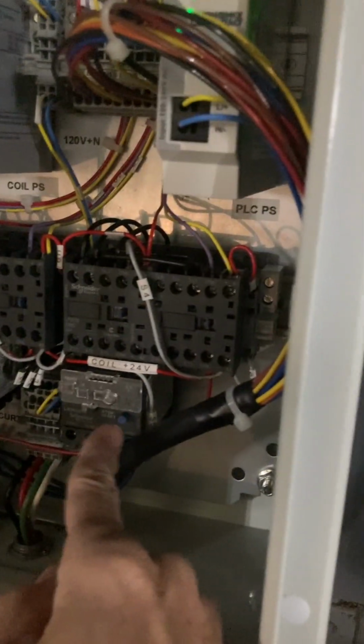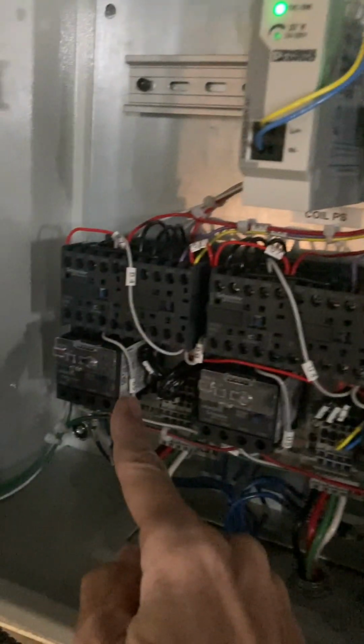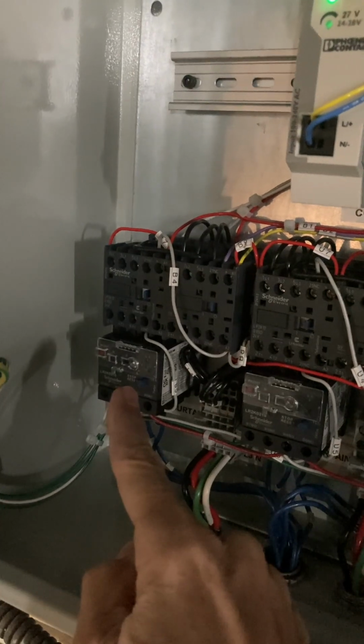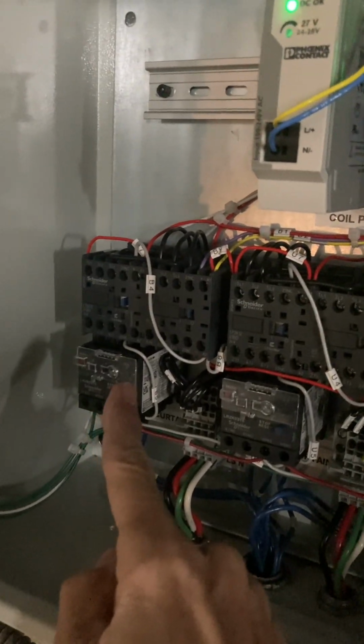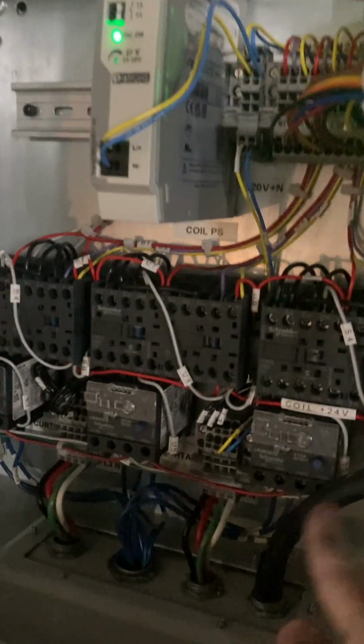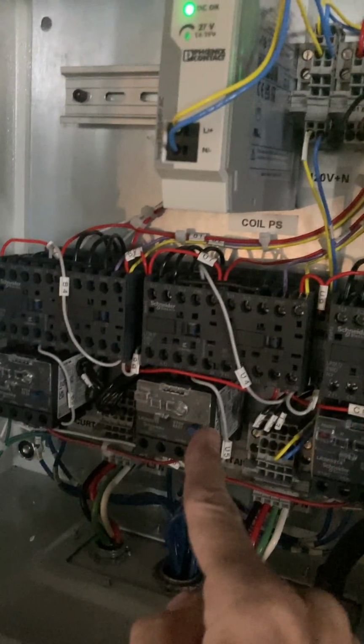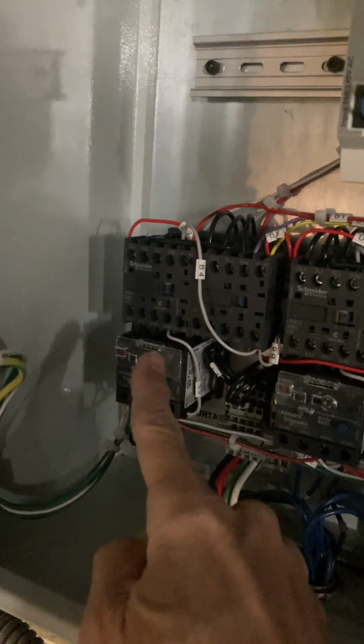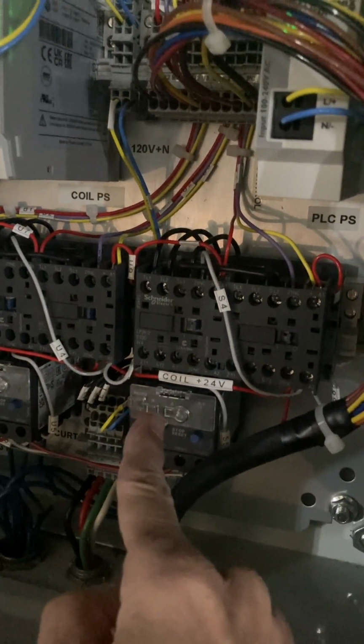Each motor has an overload and phase protector. In the event that there's an overload or a loss of phase, the yellow indicator flag will show under the window. There's also a blue reset button for each one of these, and under the window there's a red test button so that you can make sure that this is actually working.